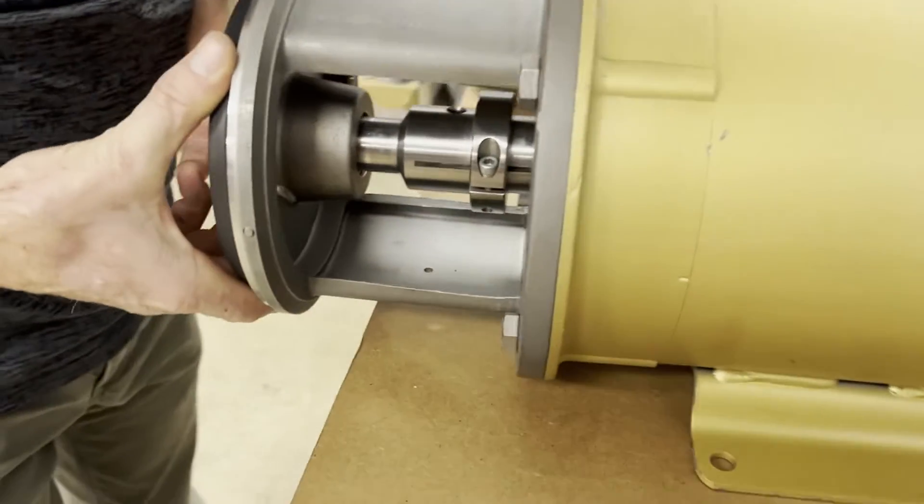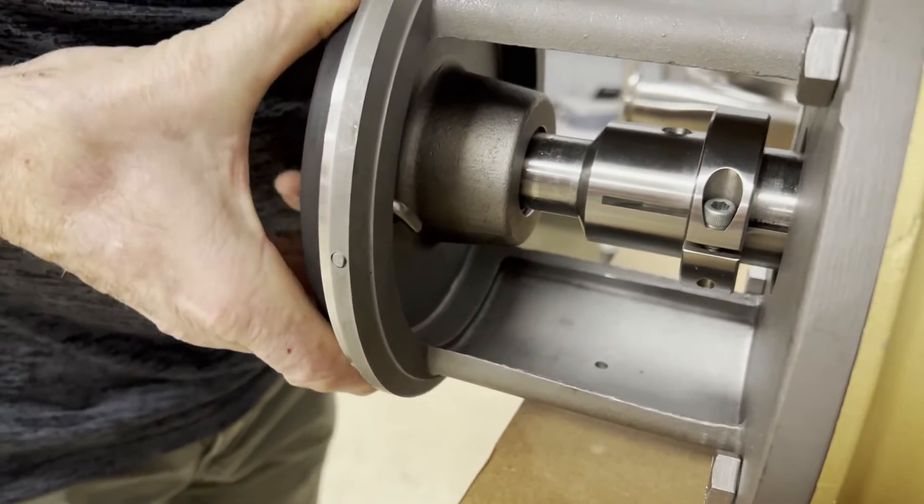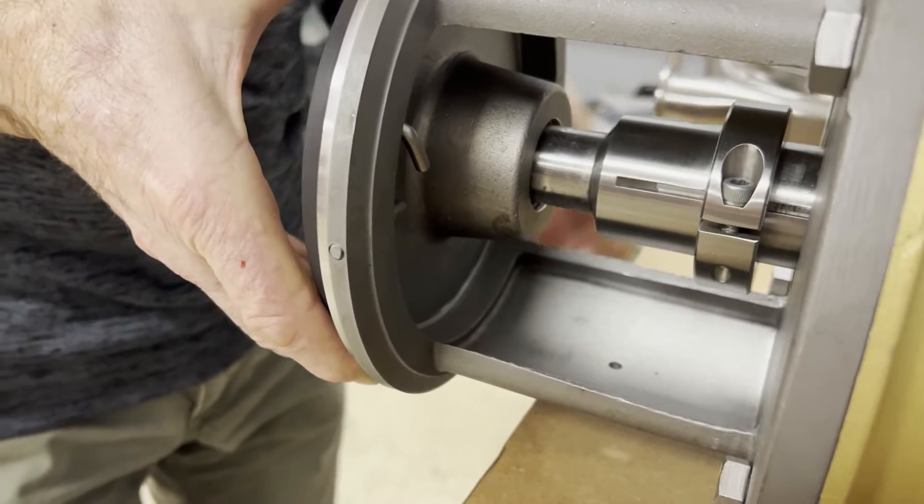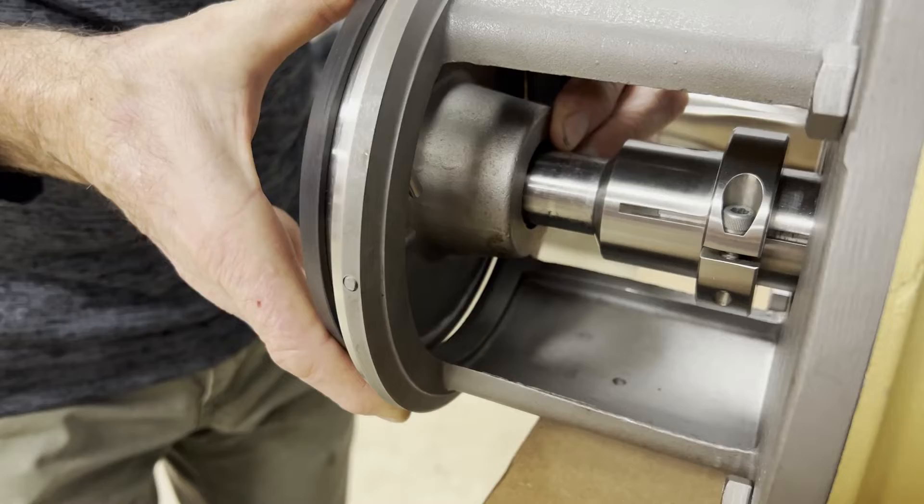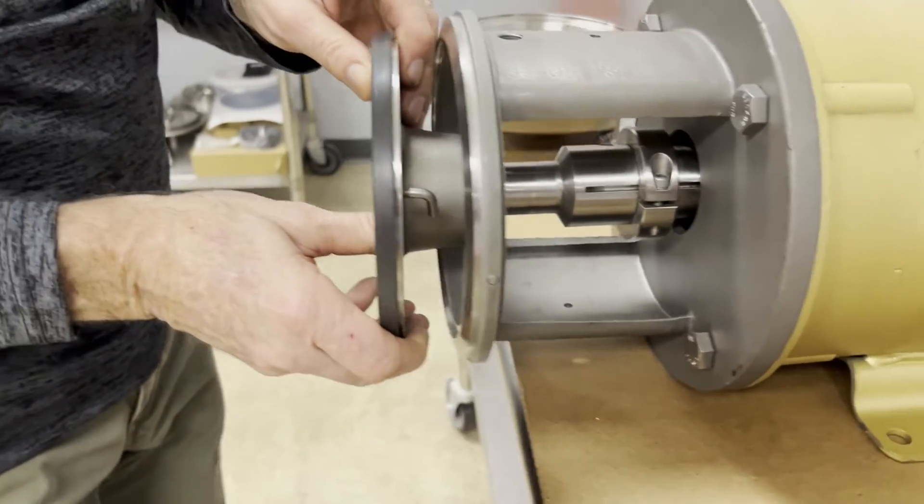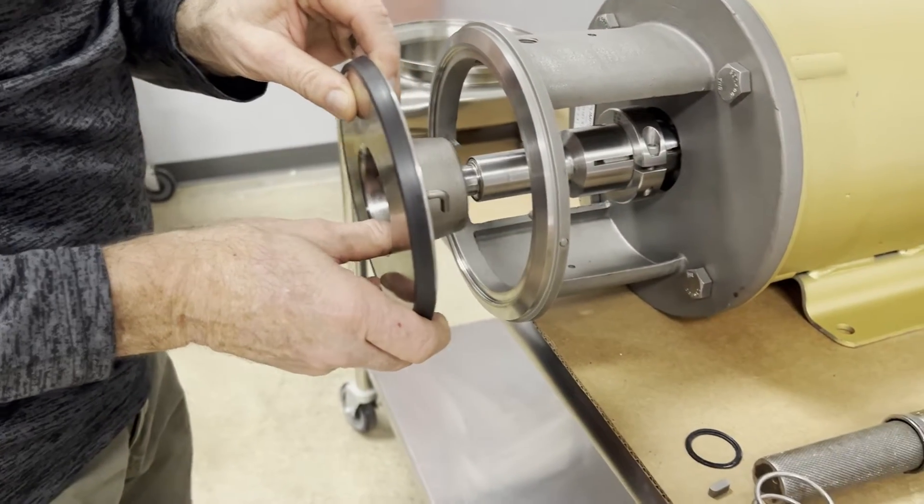At this point on the back plate there's two hooks. You want to turn the back plate about 10 to 15 degrees and carefully remove this from the adapter and stub shaft, careful not to hit the seal on the stub shaft.